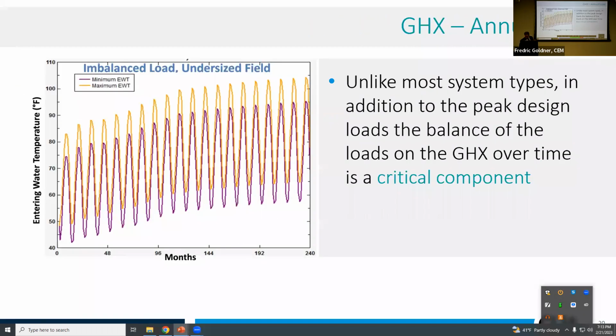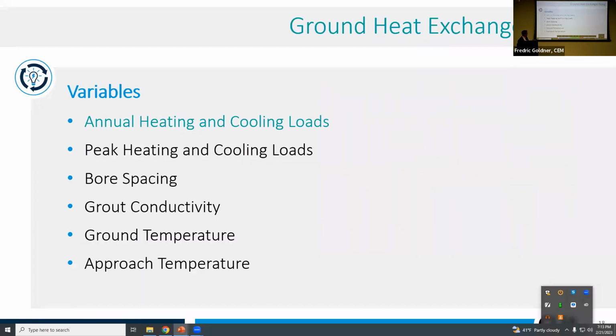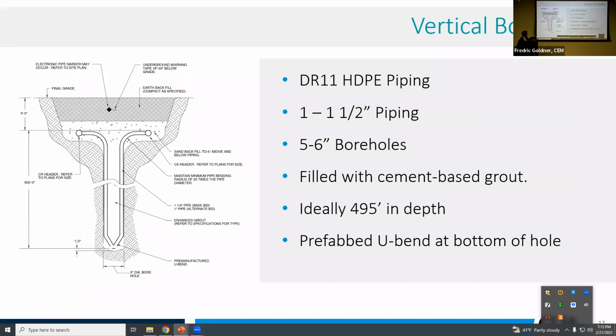Typically on the, what? We like to see 5 feet separation between the supply and return so we can keep inertia, transfer of energy. The annular space of the hole is filled with a bentonite grout or a cementous grout, so that it's just basically a solid plug. And we always like to stay below the frost line. My rule of thumb is always 5 feet, regardless of the 42 inches that we have in this area. I'd like to see about 6 inches of clean soil above and below my pipes.